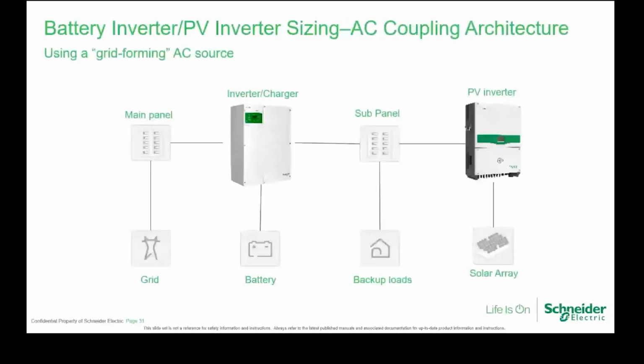When we look at the architecture, basically, if you're grid connected, you can have a main panel with a grid connection on, then it goes off to the inverter. That then hooks up to the battery bank. By the way, you do require a battery bank for the inverter charger to actually work. Then that goes off to your sub panel where your backup loads are. Now, the sub panel can then be the connection point for your PV inverter. And then you have your solar array hooked up to the PV inverter to provide solar energy that comes back through to the backup loads.